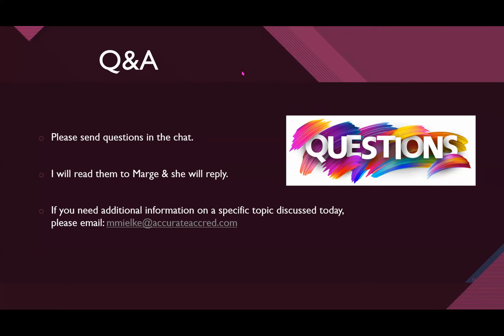We have another question from Juanita. If we don't have the original documents for equipment or construction of the facility, how do we obtain copies? Okay, so sometimes, if you're licensed in your state, they will have copies of your documents and you may be able to obtain them. So it depends on how long ago we're talking. If you have had your med gas inspected and they say you're good to go, then the surveyor probably will not ask for documentation that the above ground and below ground piping was installed as required.